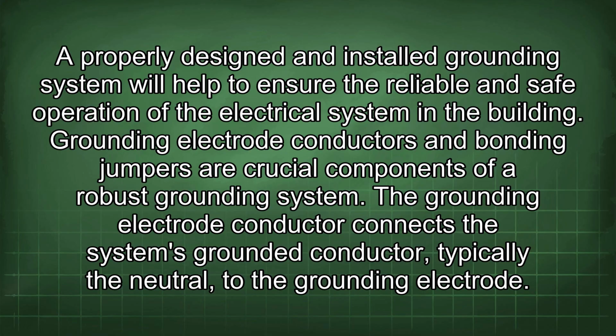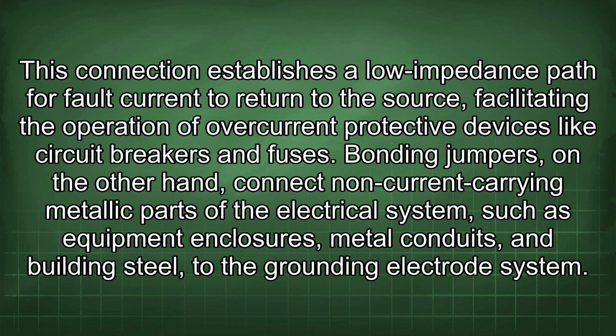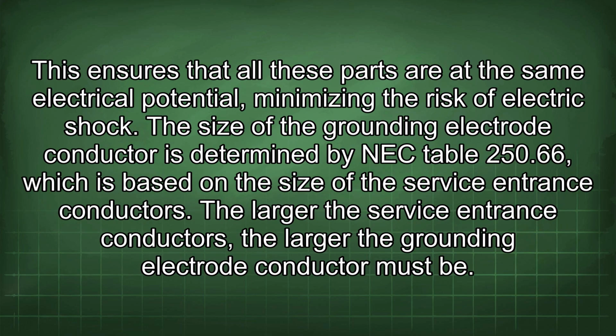The grounding electrode conductor connects the system's grounded conductor, typically the neutral, to the grounding electrode. This connection establishes a low impedance path for fault current to return to the source, facilitating the operation of overcurrent protective devices like circuit breakers and fuses. Bonding jumpers, on the other hand, connect non-current carrying metallic parts of the electrical system, such as equipment enclosures, metal conduits, and building steel, to the grounding electrode system. This ensures that all these parts are at the same electrical potential, minimizing the risk of electric shock.